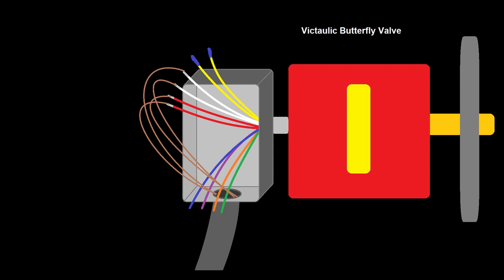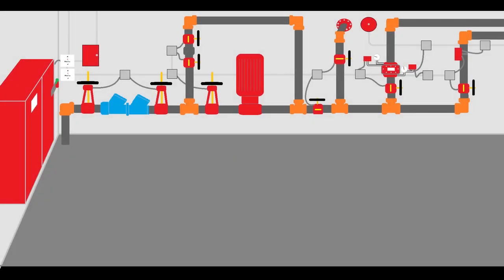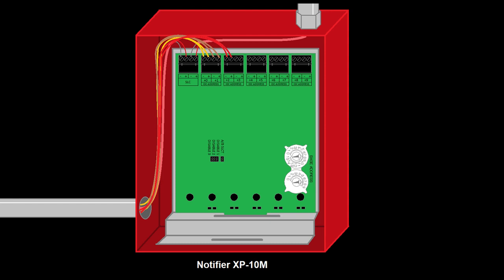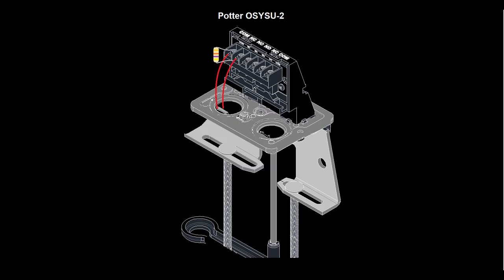Now that we've seen how to wire up both types of valve tampers, we can continue on with the rest of the valves in the room. The next valve we have to wire in is the OS&Y pump suction valve. We'll use the next available point on the XP10 and wire it to common and normally open terminals on the tamper switch, same as before. The resistor will go right across the wires since this is the only device being monitored by this point.